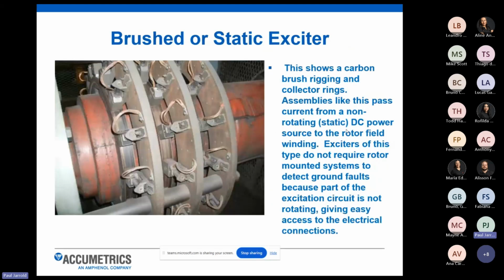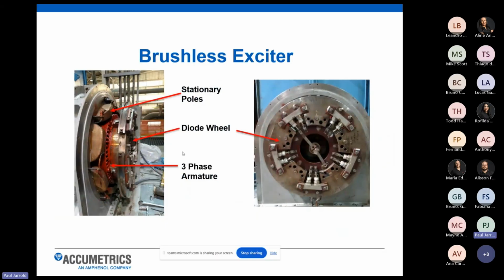So this is an example of a brushed or static exciter. You can see the brush rigging and slip rings that are on the generator rotor. So there is direct access here to the DC field voltage. And in these systems, oftentimes there is a relay contact that is looking for current to flow between either the plus or minus of the DC field and rotor ground. If there is current flowing, it'll close that relay contact to let the customer know they've got a ground fault somewhere in their field windings. So there is no need for an Accumetrics wireless system in this case, because you have that direct access to the DC field source. However, on a brushless unit, you don't have that direct access.